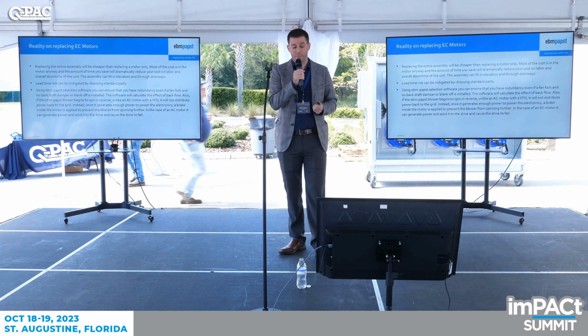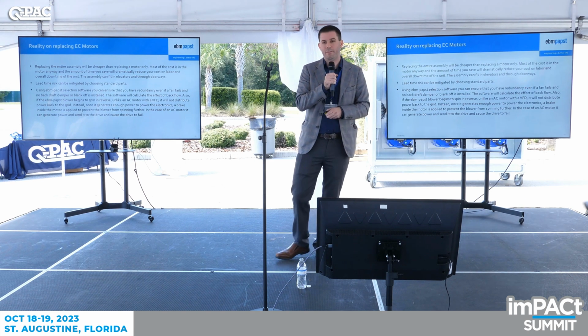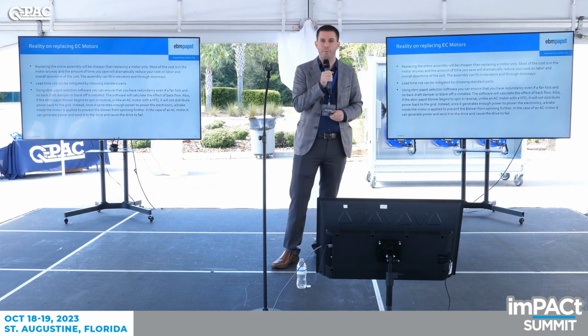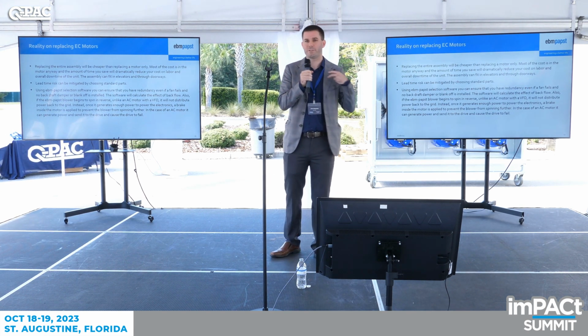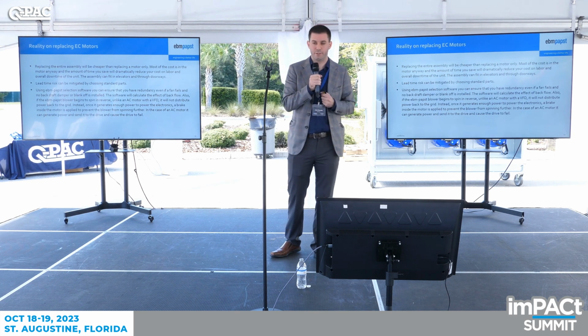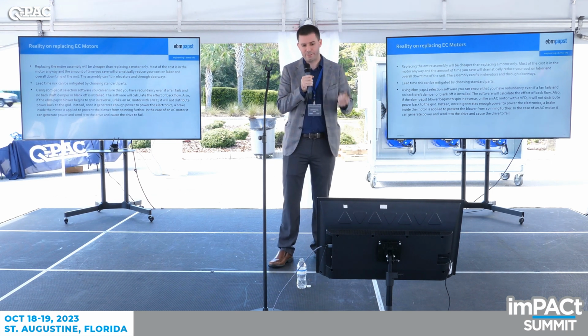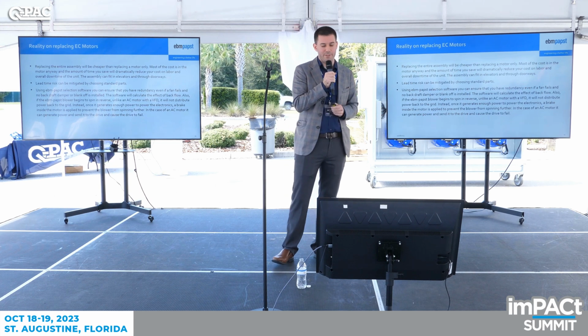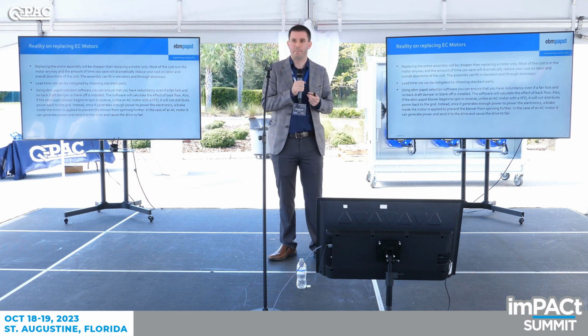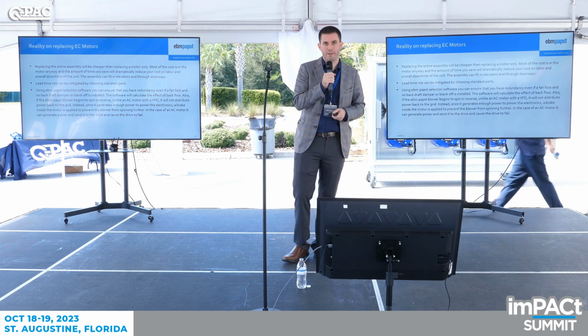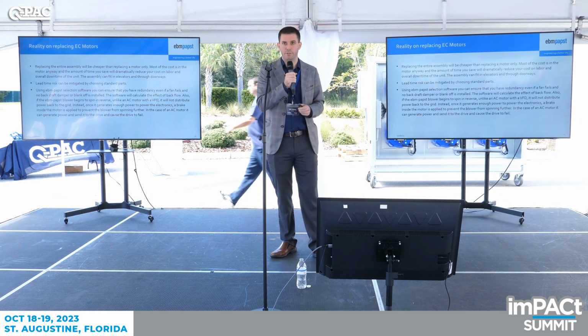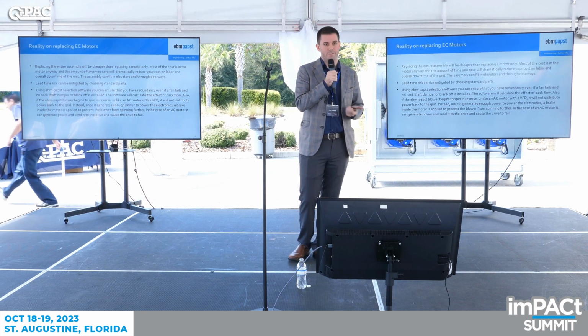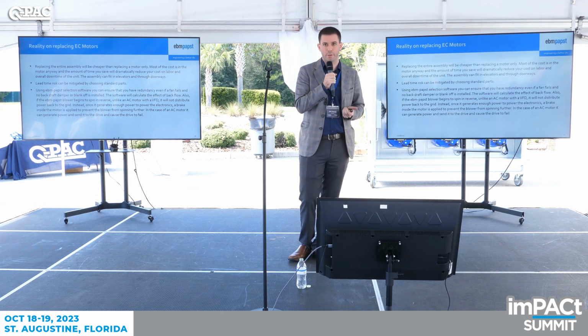So the reality on replacing EC motors is the entire assembly lots of times is going to be cheaper than replacing the motor only when you factor in all the extra costs of what you have to do. So the extra downtime of the unit, if you actually get a balancer out there. Lead time risk can be mitigated by choosing standard parts as well as by localized production. So having production in America now means that the lead time on those parts is very, very short.